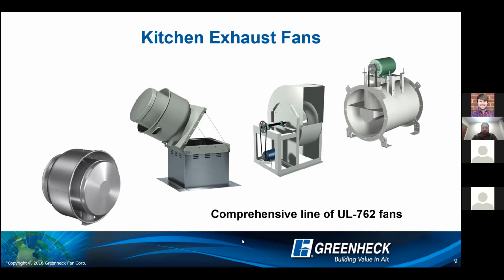The other question I get from engineers quite a bit is, do I need a vented curb or just a standard curb? The answer really is that it differs by municipality. And it depends if they're wrapping their fire duct with insulation all the way up to the intake of the exhaust fan, or if they're stopping the insulation wrap at the roof deck. If they're stopping it, you would need a vented curb.